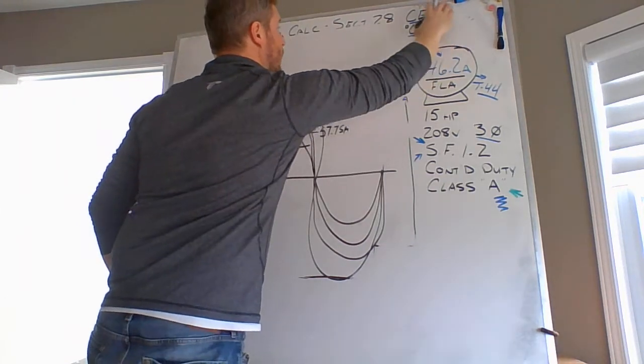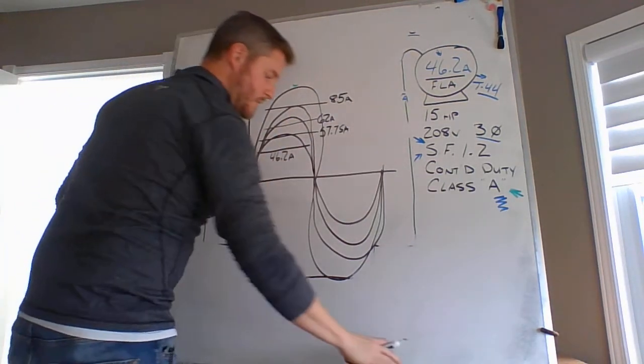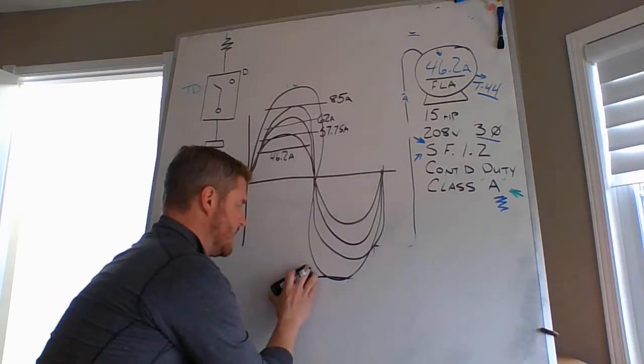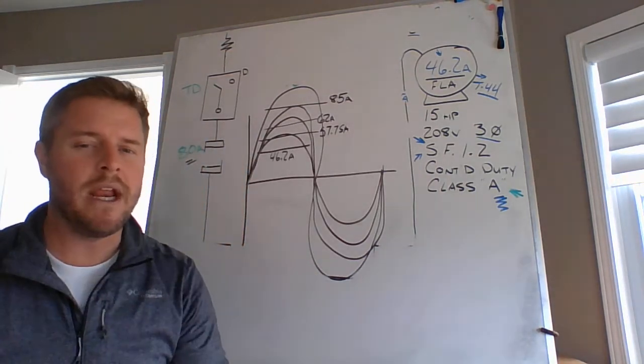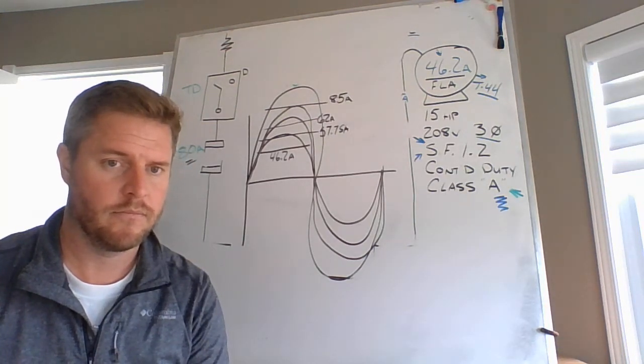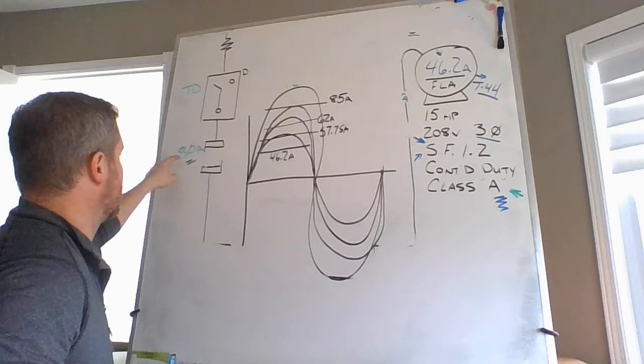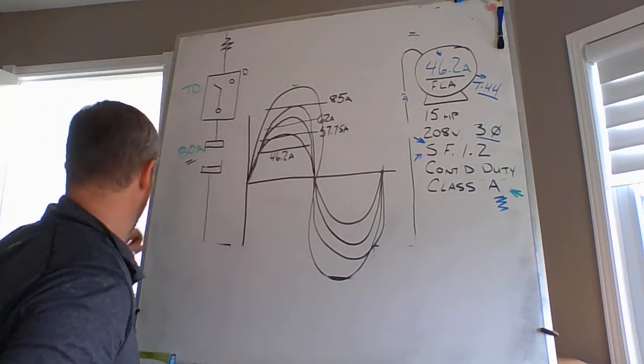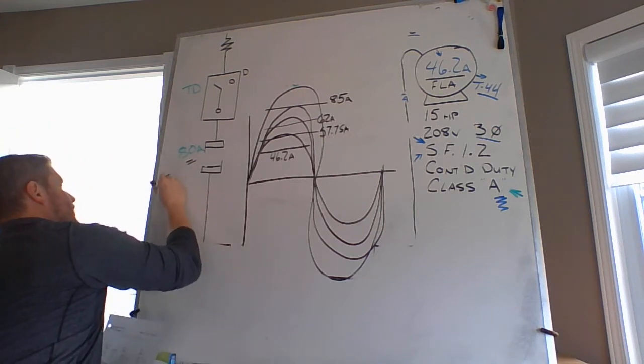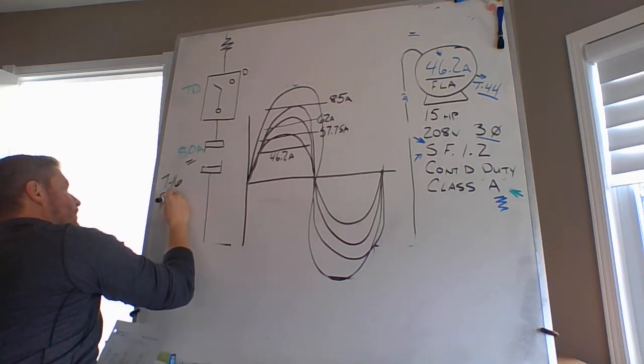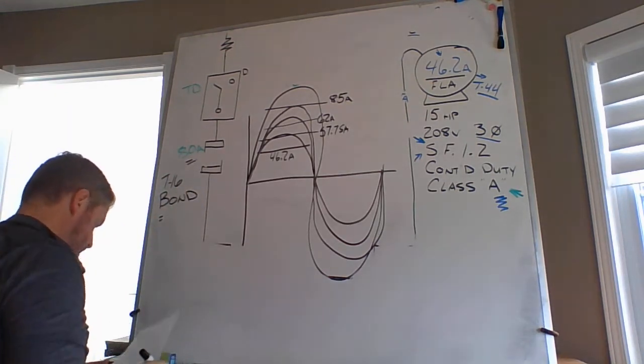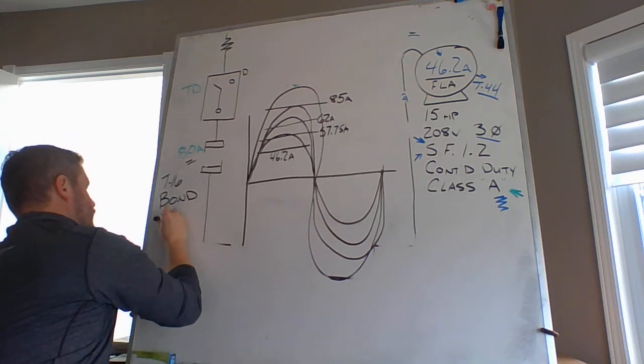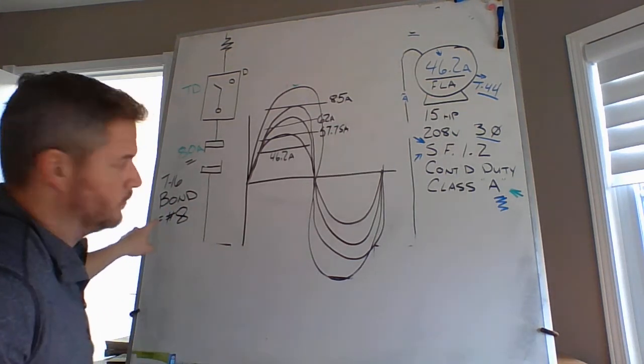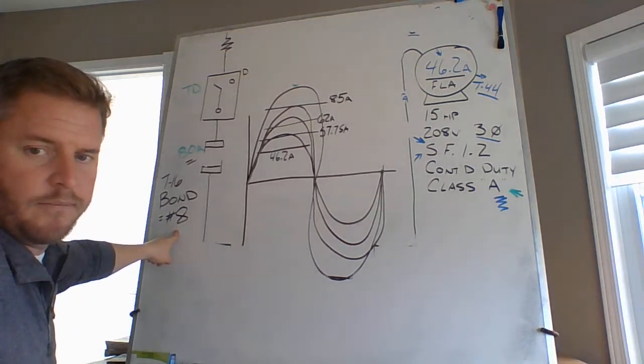We know what we're installing. We have an idea of what's actually going on. We understand what's going on with this one specific motor calculation. What ends up happening with that overcurrent device is it's actually observing and watching and waiting for a fault. For an 80 amp overcurrent device for this specific motor, I'll just give it to you right now, coming from table 16, our bonding conductor should have been a number 8. It would be a number 8 coming from table 16.